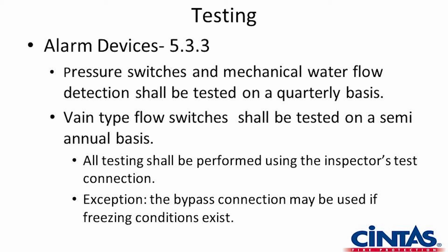Vane type switches shall be tested on a semi-annual basis. All testing shall be performed using the inspector's test connection. The exception is that there's a bypass connection that can be used if freezing conditions exist. So if we're doing an inspection and flowing water in a cold environment is going to cause an ice slick in the parking lot, they give us a provision to open an alarm test line that takes water to the pressure switch.